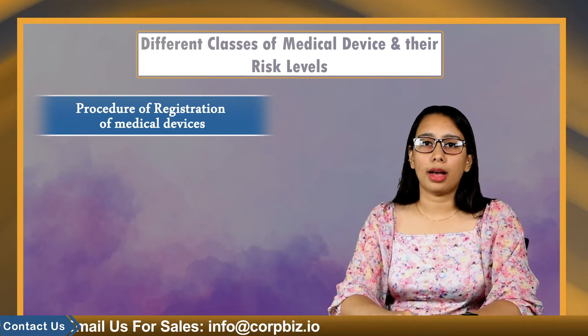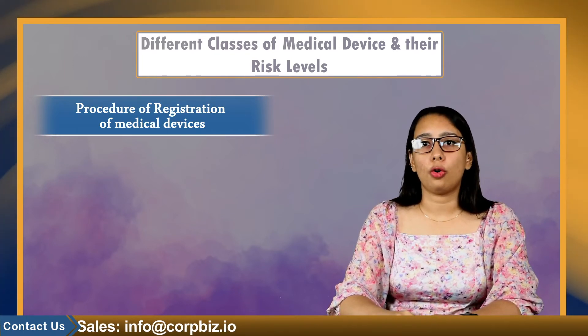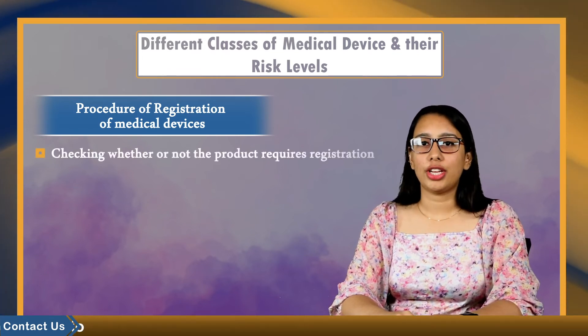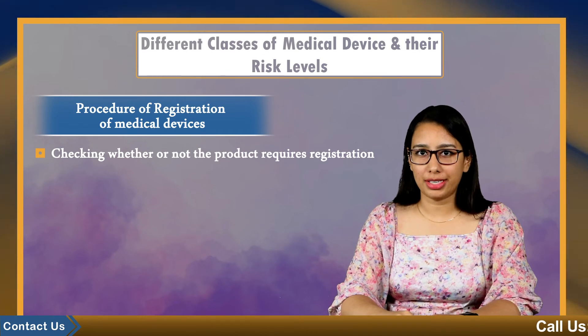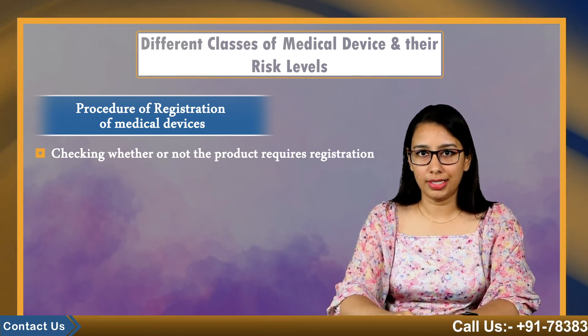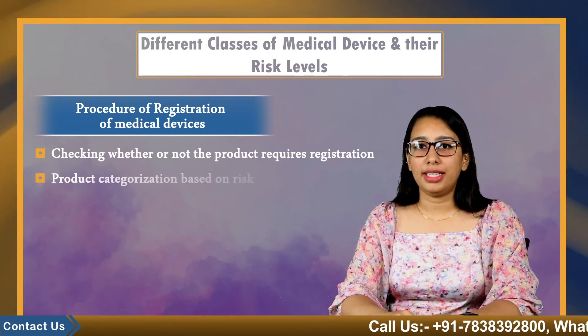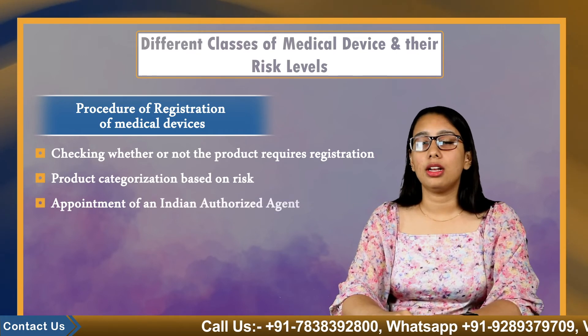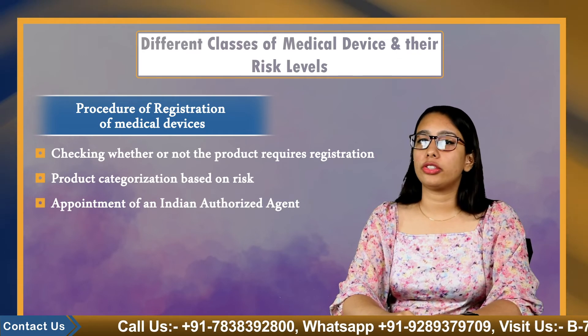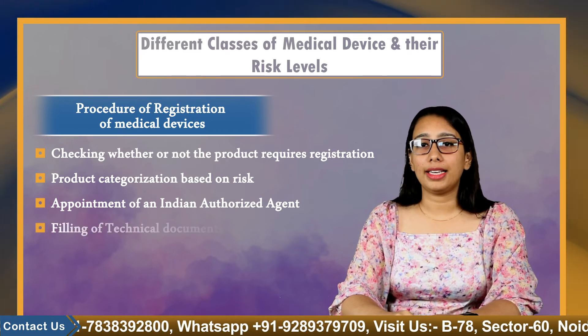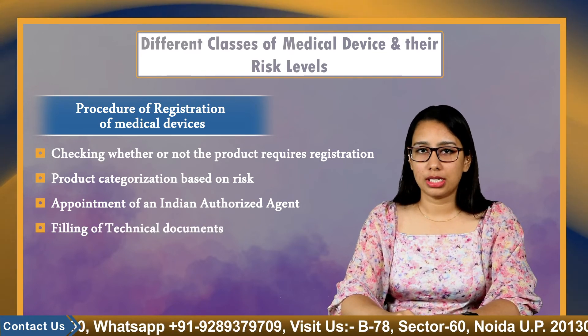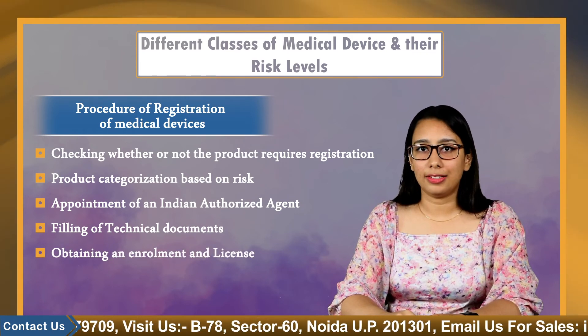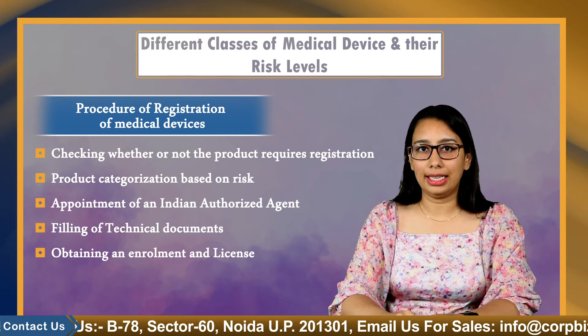Now let's learn about the procedure for registration of medical devices. First, checking whether or not the product requires registration. Second, product categorization based on risk. Third, appointment of an Indian authorized agent. Fourth, filing of technical documents. Fifth and the last step is to obtain a registration certificate and license.